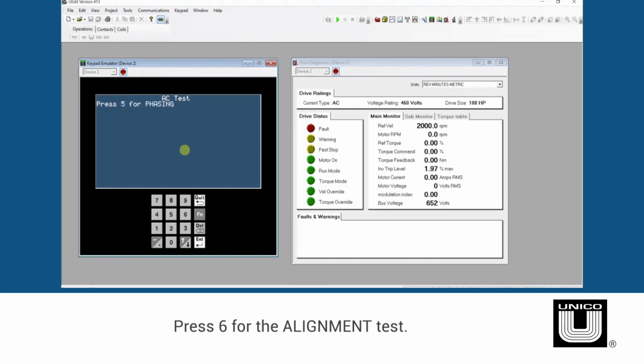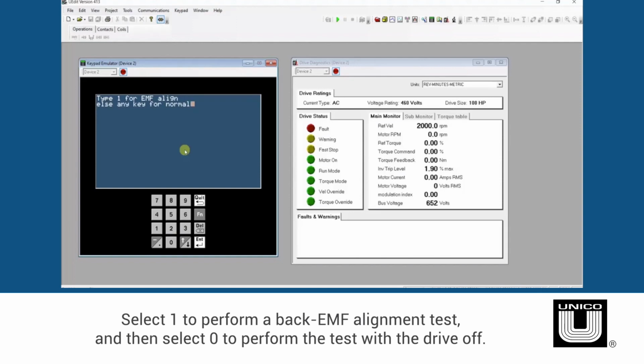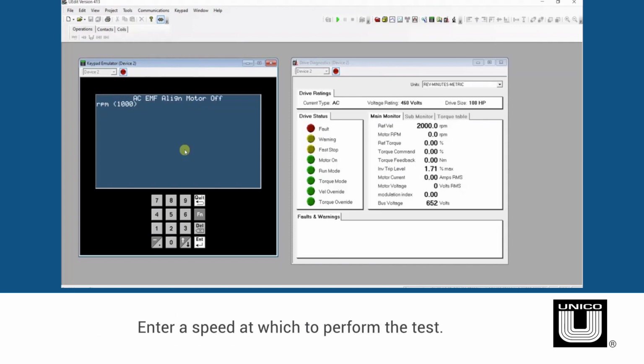Next, select 6 for the alignment test. Select 1 to perform a back EMF alignment test, and then select 0 to perform the test with the drive off. This specific test requires a load motor to spin the IPM motor, so enter a speed at which to perform the test. This speed should be less than or equal to 1/2 of the rated speed.